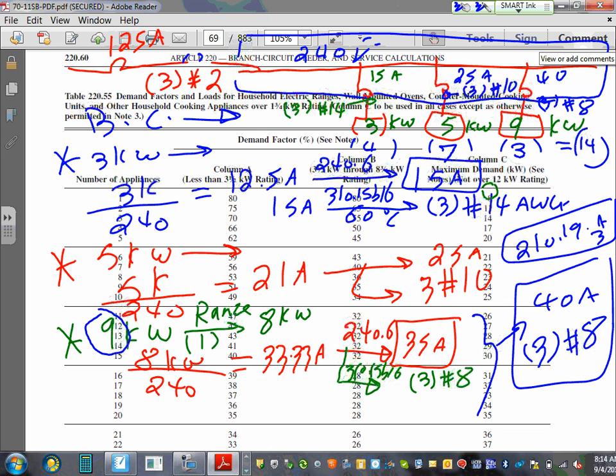Okay, I want to take one more example, guys. Any question before we go? Karen, does it make sense? If I give you a system like this, would you guys be able to handle it? Let me summarize one more time. First, we size the feeder. We size the feeder in 2 ways. Number one, if they're all 12 or under, you go to C and size it. Done. If some of them are under A or B, please apply A to the A and B to the B. And then the rest of them will be under C, apply to the rest under C. Add them up. Choose the smallest number. And then size your feeder.